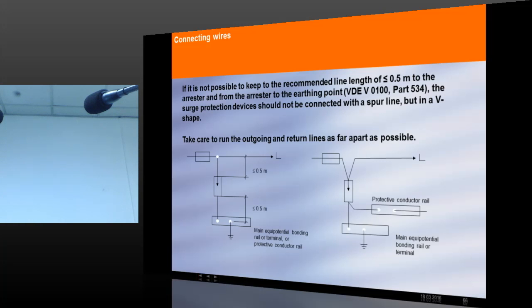And now, whenever we install an SPD, imagine that you want to install an SPD in an existing panel board. There is a panel board, let's say at this place, and you want to install an SPD. What will we do? We buy the SPD, maybe with a box, keep it outside the panel, take long wires and connect. If we use long wires, see in this particular case, a wire in parallel from the line to the SPD and from the SPD to the bus bar, the maximum allowed length is, I have shown 0.5, but in the new standard it is reduced to 0.25. That means, in simple terms, use a very short wire to connect an SPD. The thickness of the wire is not very important, but the length of the wire should be as short as possible.